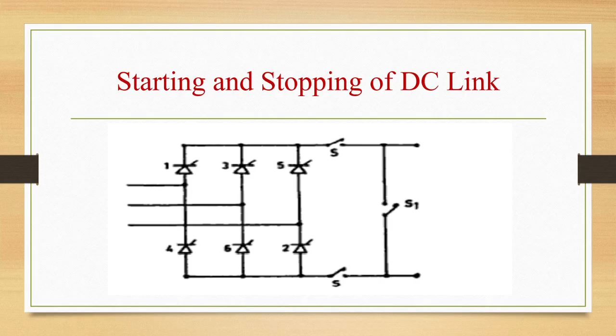In the case of a predetermined choice of the bypass path, time lapse between the blocking command and the current transfer to bypass path can vary from 60 degrees to 180 degrees for a rectifier bridge. This time can be reduced from 60 degrees to 120 degrees if the bypass pair is chosen such that the valve with the lower valve number carrying current at the instant of blocking is included in the bypass pair. In the inverter, there is no time lag involved in the activation of the bypass pair.